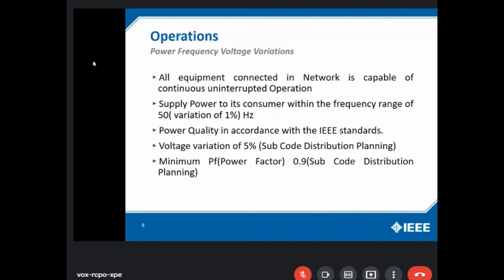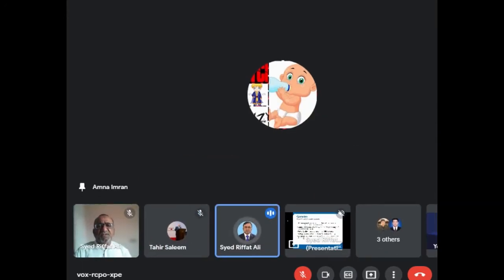Then there are power limitations for the power frequency voltage and the power factor as well. All the equipment connected in the network is capable of continuous uninterrupted operation. The second point is to supply power to each consumer within the frequency range of 50 hertz, and of course, plus or minus 1% of variation is allowed, and that comes out to be 0.5 hertz. And the power quality in accordance with the IEEE standards, which deals with the harmonics level. Voltage variation of 5%; sub code distribution planning can be referred to for these details as well. And the minimum power factor is 0.9. Support distribution planning can also be referred to in this case as well.